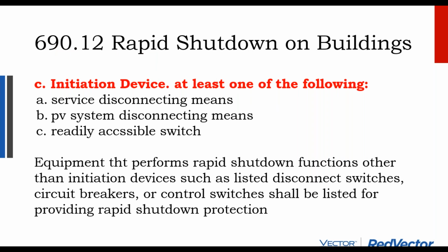And so the rapid shutdown device can be kind of any kind of switch. It doesn't have to be a knife switch disconnect. There's a separate requirement for knife switch disconnects to isolate the home from the electric grid. The knife switch disconnect is also useful when the building's on fire, to make sure the building's isolated from the grid, but it's not quite the same function as the rapid shutdown device, even though your AC knife switch disconnect can initiate rapid shutdown. It doesn't have to be what initiates rapid shutdown.